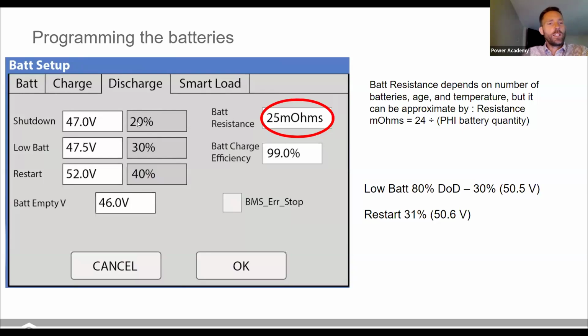If you're only cycling once every few days, then 10% is fine. If you're only cycling it during an outage, then just set this at 0%, and that allows a full discharge cycle to happen on the batteries. Even at 0%, 100% depth of discharge, you're still looking at thousands of cycles on these batteries. 365 cycles would be a year, right, if you did that daily.